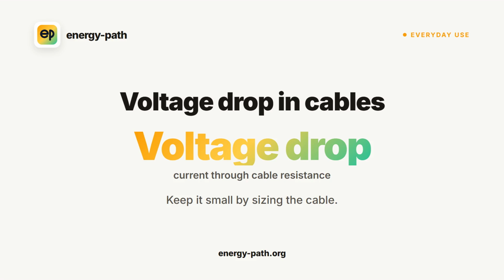The law is also your fault-finding tool. Measure the voltage across something and the current through it, divide one by the other, and you have its resistance. Compare that to what it should be and you can spot a fault.